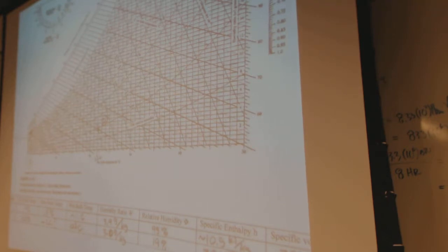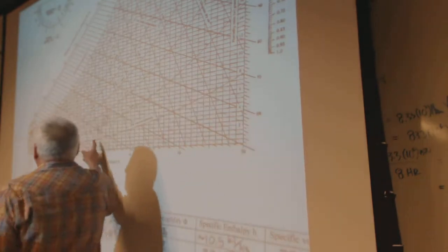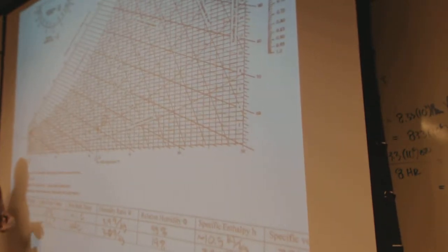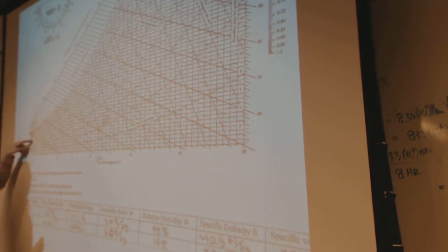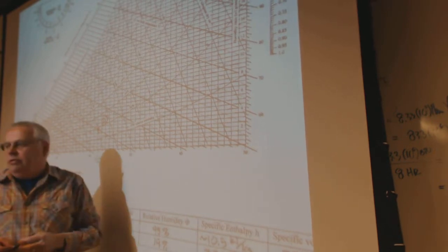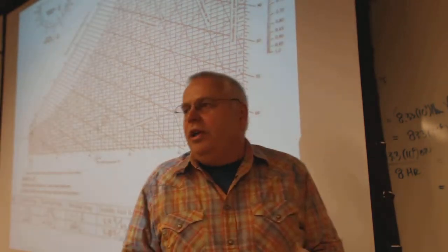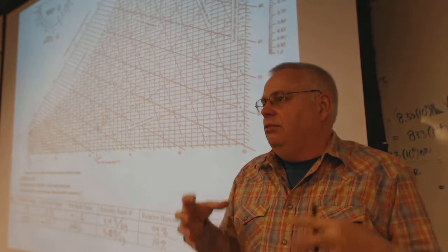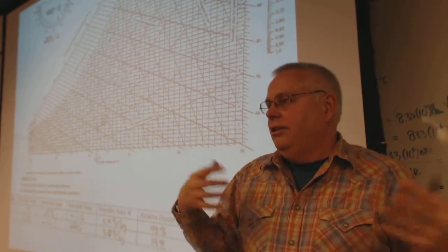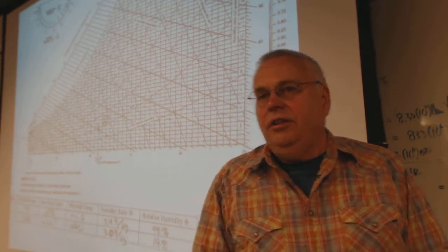Now let's use it for something. I mean, great, we found all this stuff, big freaking deal, right? What this shows me is there's more moisture outside now, and things are melting and it's coming up. But because the moisture's lower in here, they're not dehumidifying. It just tells me we're not exchanging a bunch of air, we're saving energy. So this is yesterday's air from when it was 20 degrees in here.